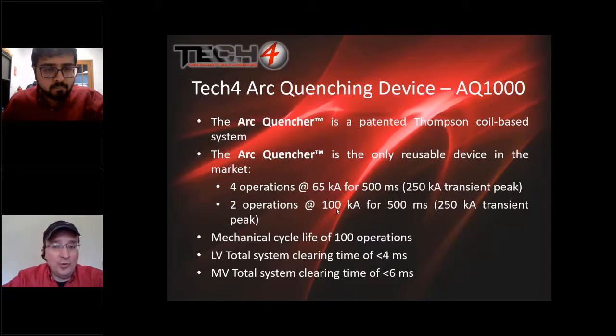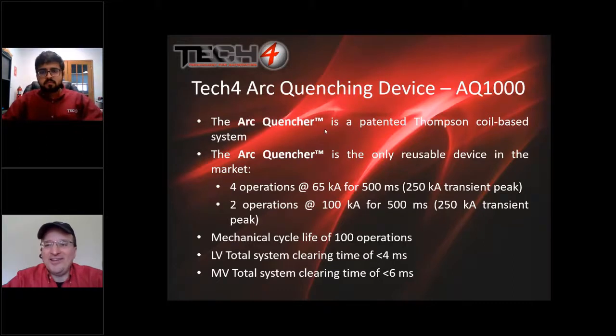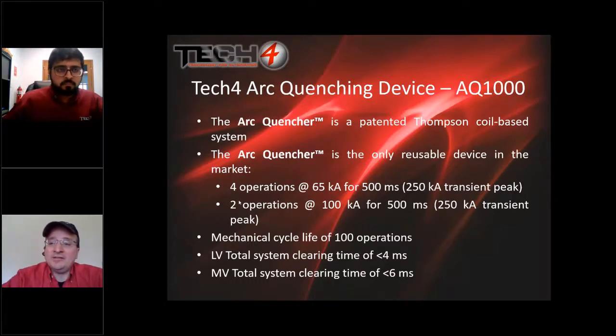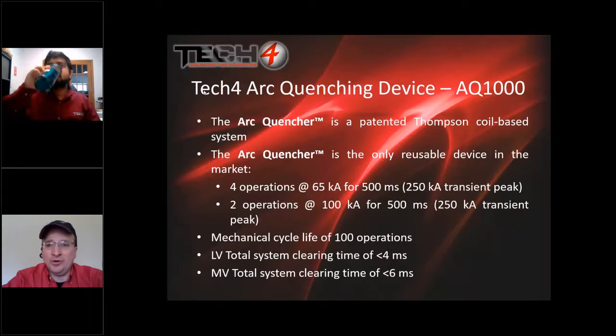Whether it's 4 operations or 2 operations, resettability is important, but this is even more important to remember if you are an electrical plant engineer responsible for the system. Arc flash events in any single facility on any single circuit should be rare. Nationwide, yes, we get anywhere between 6 and 8 arc flash events per day. But in a single facility, and on a single circuit especially, having more than 1 arc flash event is absolutely indicative of either poor work practices or poor equipment condition, or both.